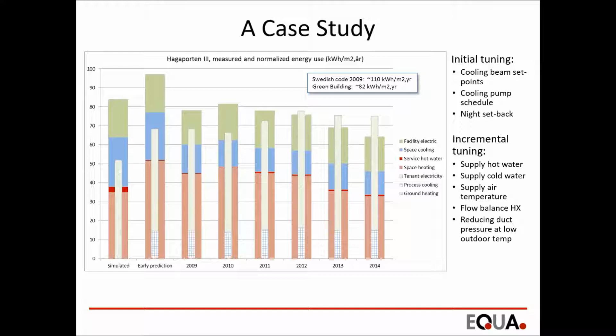So we didn't really do any sophisticated things. We just looked at data, tried to think, and then changed the settings of the control systems. So the only things that were changed were schedules and set points. There was no refurbishment or changing of any components or anything like that. Just control settings. And so I think the message is quite clear here, and that is that we could save more than 30% of energy just by tuning the control system, basically. Maybe we should mention here also that we didn't touch the fan operation schedule. Otherwise, that's a very easy way to save energy, but that was fixed over the years.